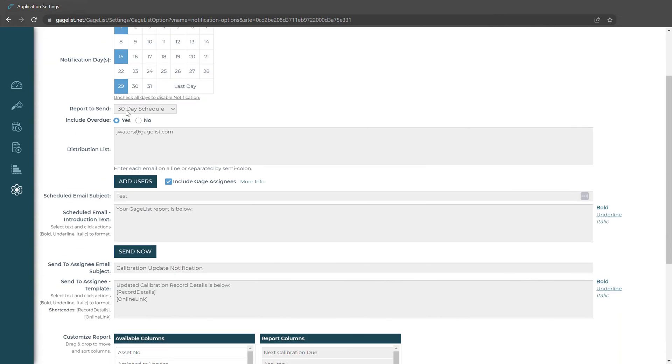We can choose the report that gets sent. Here we have a 30-day schedule so any gauges coming due in the next 30 days will be sent in that report. We can choose all the way from 7 to 180. We can also choose to include overdue gauges.